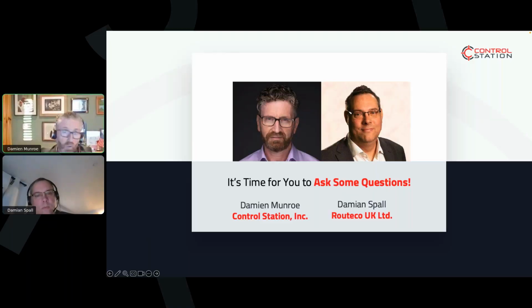Really, it's as I said earlier about the dead time - dead time is the killer of good control. Understand the process by which, when our valve changes, we see that in that value. The valve opening, heating up of the system, is going to be much slower when you're turning on that system for the first time - dead time's going to get longer. But if you're up and operating, once you make a change to your valve, it's going to then impact the process. A rough rule of thumb is how far away your instrument is downstream in your pipework, and how many meters per second it takes for the liquid in the heat exchanger to reach your instrument. If your instrument is 1 meter down the pipe or 10 meters down the pipe, and your flow rate is 1 meter per second, you're adding 10 times the dead time to that process.